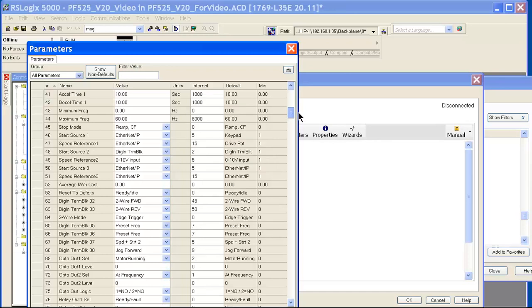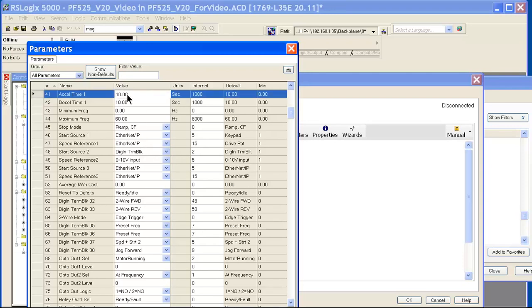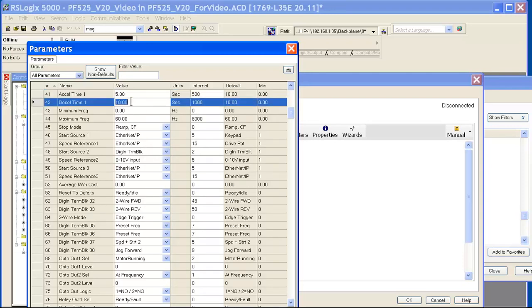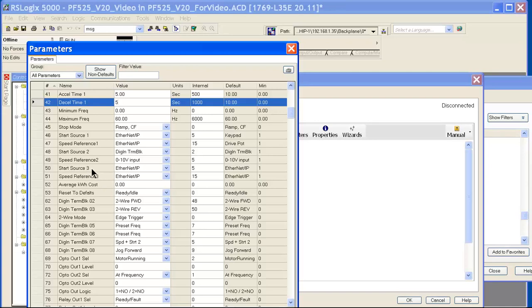You would make the changes to whichever parameters you wanted as far as your maximum frequency you want to run, what your drive is, what mode you want to operate in. For the most part, you're going to just change maybe your start-stop source, maybe you want to change your accel time from 10 to 5 seconds, your decel time from 10 to 5 seconds, what your maximum frequency is. Notice with the PowerFlex 525, my start source is automatically set to Ethernet IP because I'm putting it in RSLogix 5000. It knows that I'm probably going to want to control it using Ethernet IP.